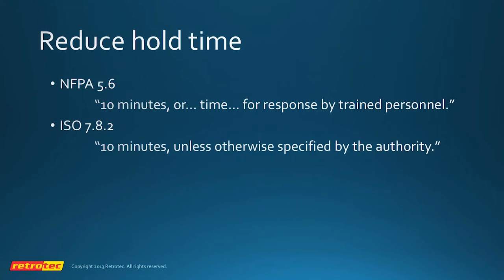In some cases, for really small enclosures, you may want to consider reducing the hold time. For isolated enclosures, we may want to increase the hold time. But for very, very small enclosures where you have operation staff there 24 hours a day, then you may want to consider reducing that simply because it's very, very difficult to get those enclosures to pass.